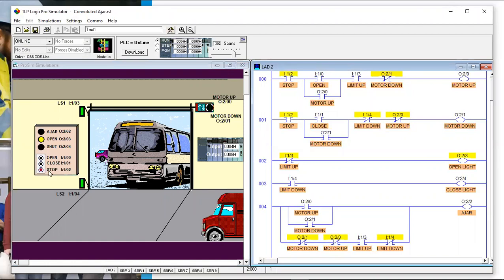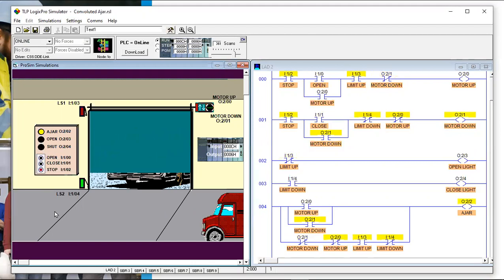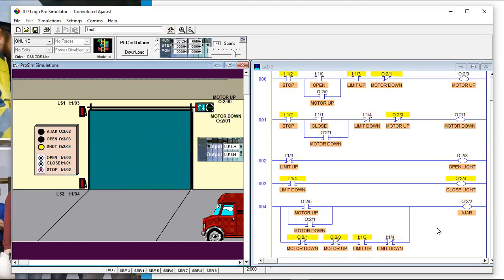Our open light is on. If we close it, we should see the ajar light come on — yes, it works. But look at what they've done: they've combined AND and OR statements, saying if the motor is running up OR it's running down — and with another OR around this — and if it's not running down and not running up, then throw the position of the other limit switches in there as well, then turn on the ajar light.